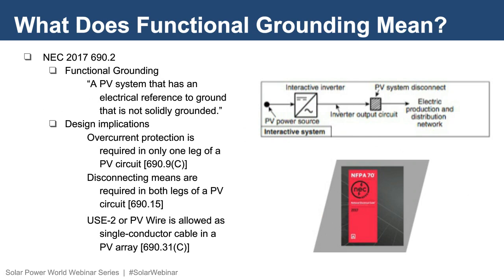The introduction of the definition of functionally grounded, a PV system that has an electrical reference to ground that is not solidly grounded, has many design implications that the PV industry will benefit from. The most important is that we will now apply a single set of design parameters to both functionally grounded and ungrounded PV systems. Major implications include the reduction of overcurrent protection in circuits. Disconnecting means are required in both legs of a PV circuit, and the use of USE-2 or PV wire and single conductor cables are both now allowed to be used within PV arrays.